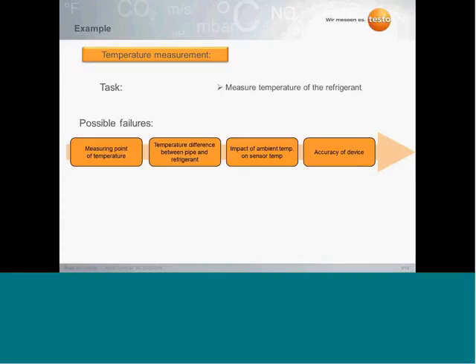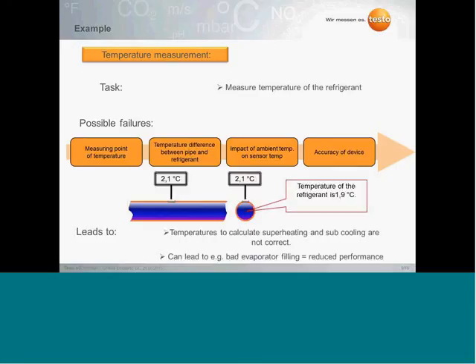Also, we have differences in the accuracy of the measuring devices. This again, of course, leads to wrong absolute temperatures, and then to wrongly calculated superheating and subcooling values. We will have an impact on how the system is set up, of course.